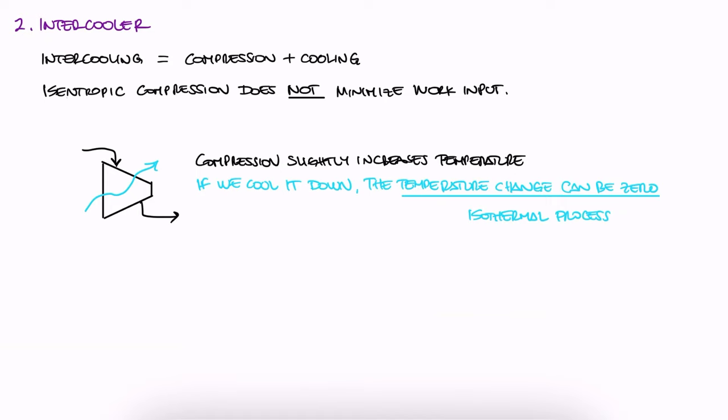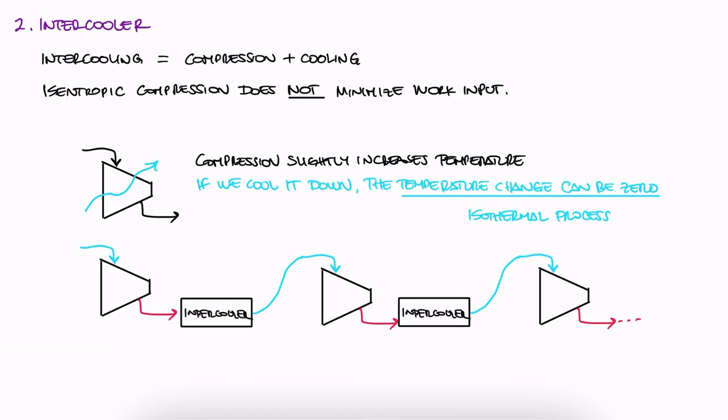In reality, what we actually do is compress, remove heat, compress, remove heat, etc. The more intercoolers you use, the higher the efficiency, but at some point, the increase in efficiency is not worth the extra complexity of the system. So, a typical arrangement includes two of these intercoolers, which will improve overall efficiency enough.